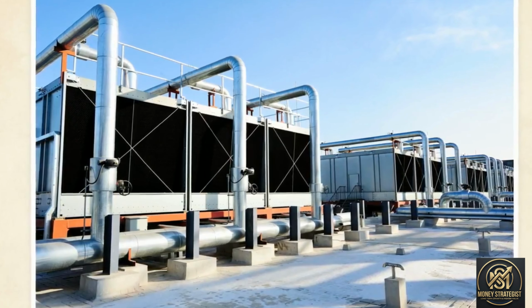This heavy reliance on water evaporation is driven by carbon accounting. Technology conglomerates have committed to net zero emissions targets, which requires them to optimize their power usage effectiveness. PUE is a ratio measuring how efficiently a data center uses electricity, comparing total facility power to the power actually reaching the computing equipment. A more efficient PUE means lower carbon emissions. The best way to lower the electrical cost of cooling is relying on evaporative water systems. Lowering the carbon footprint degrades the facility's water usage effectiveness, or WUE, the ratio of water used for cooling against electricity delivered to the hardware.